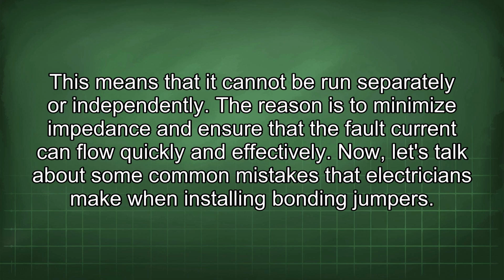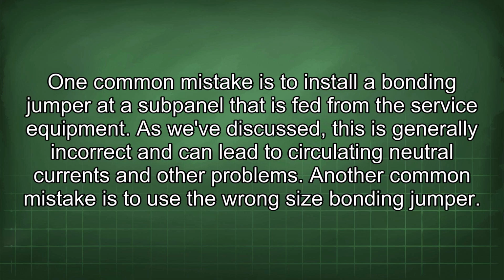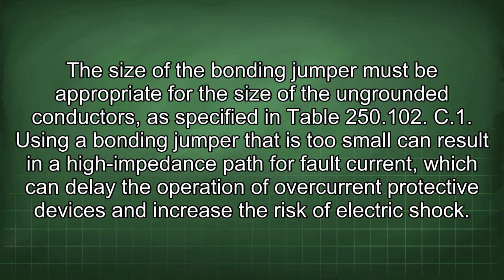Now let's talk about some common mistakes that electricians make when installing bonding jumpers. One common mistake is to install the bonding jumper at a subpanel that is fed from the service equipment. As we've discussed, this is generally incorrect and can lead to circulating neutral currents and other problems. Another common mistake is to use the wrong size bonding jumper.